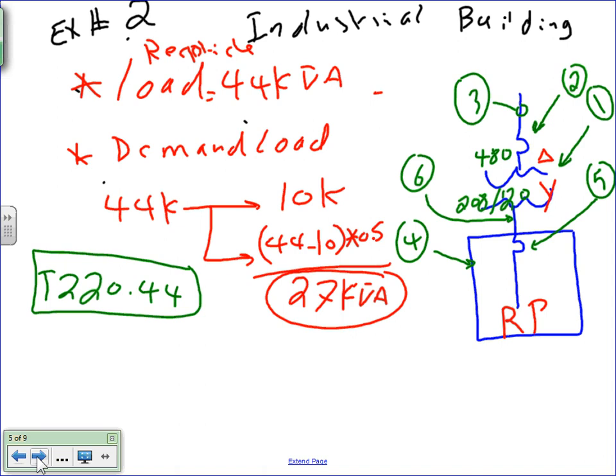Okay, now, please be aware of this one. This is a receptacle panel. So I assigned that to my friend, and he put 44 kVA load of receptacles, and I need to find the demand. This is just receptacle load. Basically, you took 180 multiplied by how many receptacles, you came up with 44 kVA. I need to demand them. Everybody knows how to demand it. The first 10K from 220.44, the first 10K, leave them alone. Anything higher than 10, cut it by half and add. Don't forget the word add. Any question, guys, about this slide? So the number that I came up with, 27 kVA, is the demanded load for the receptacle. Demanded.